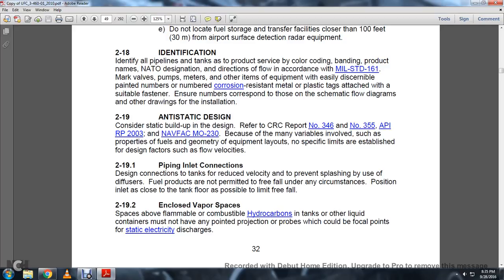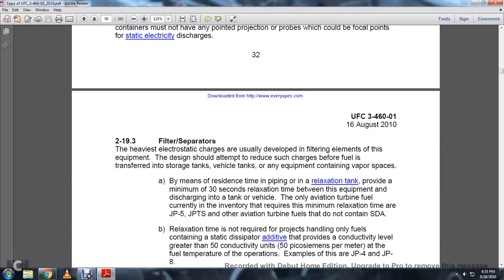2-19.2 Enclosed vapor spaces. Spaces above the flammable combustible hydrocarbons in the tank and other liquid containers must not have any pointed projection or probes which could be focal points of static electrical discharge.